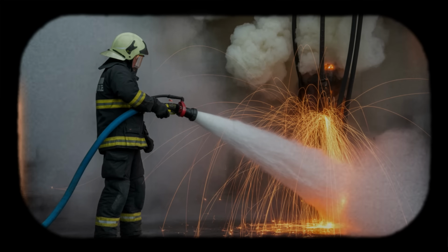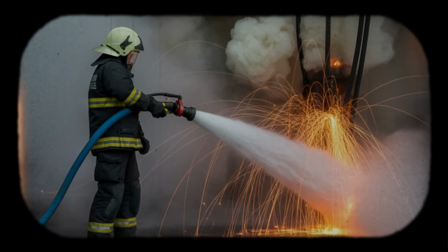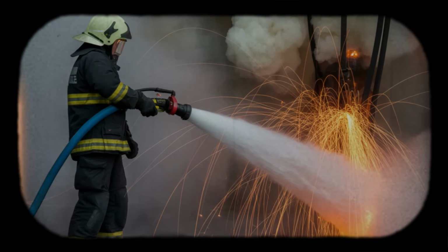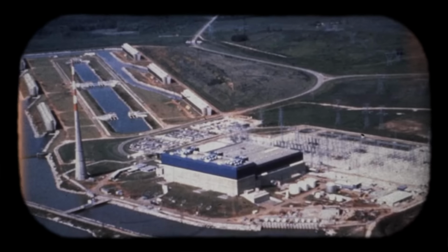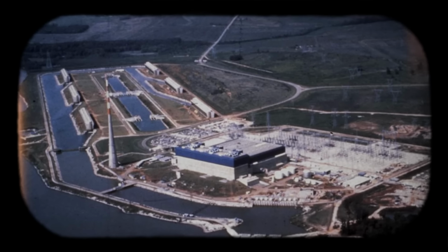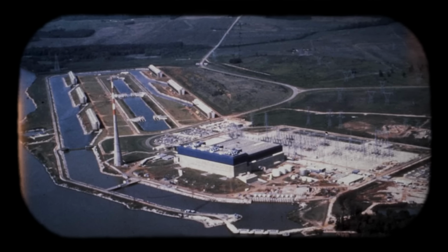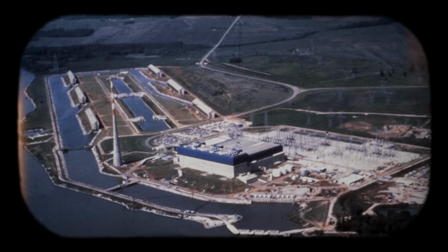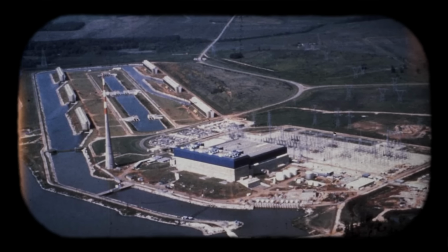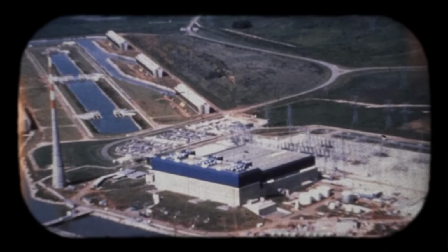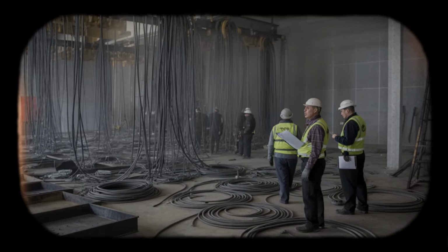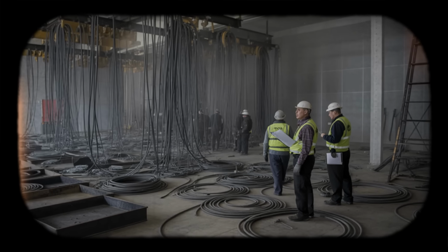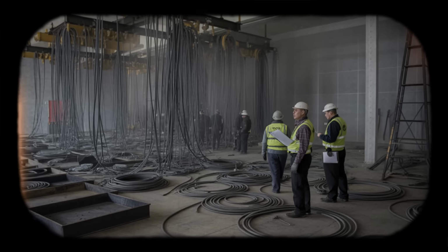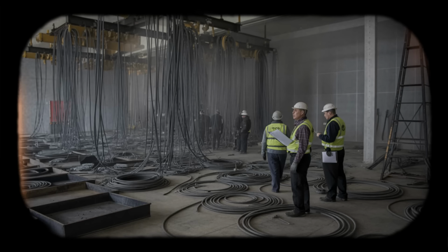The numbers tell the scale. Over 1,600 cables will ultimately be found damaged in the fire. 200 control circuits will require complete replacement. This is in a facility designed so that no single initiating event could disable multiple safety systems. The common mode vulnerability created by shared cable routing was not identified during design, construction, or licensing reviews. Operators relay orders by radio to field personnel.